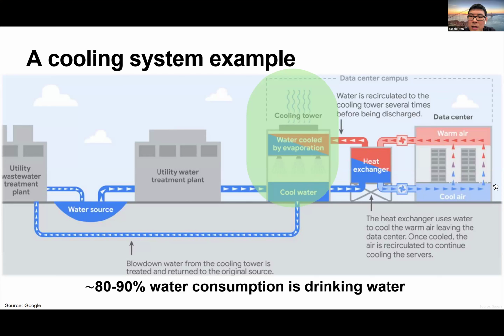In any case, there shouldn't be any water loss or water consumption between the servers and heat exchanger, unless there's a leak, but that's an abnormal scenario. Once we transfer the heat from the servers to the heat exchanger, we cannot accumulate the heat at the heat exchanger forever. We have to further move the heat to the outside, and this is where the water consumption comes in.